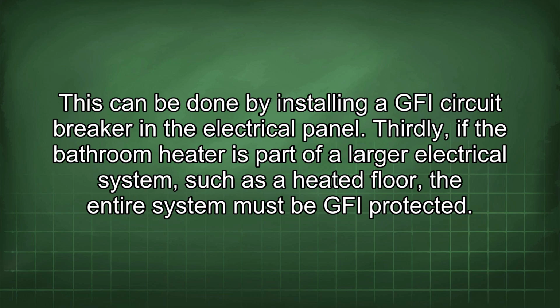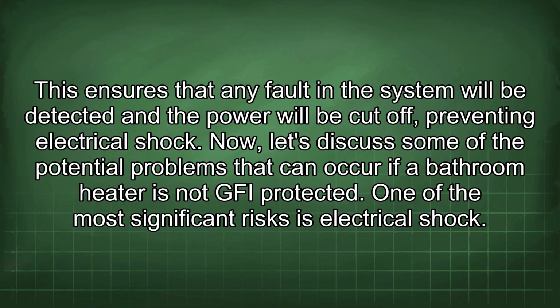Thirdly, if the bathroom heater is part of a larger electrical system, such as a heated floor, the entire system must be GFI protected. This ensures that any fault in the system will be detected and the power will be cut off, preventing electrical shock.